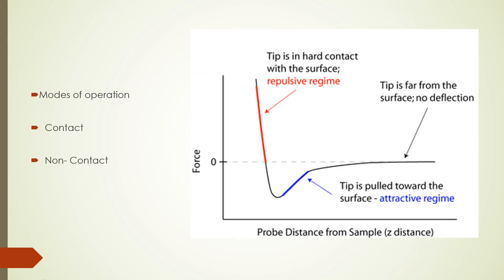The atomic force microscope has two modes of operation: contact mode and non-contact mode. Looking at the force profile, there are two regions — one in which the force is repulsive and one in which it is attractive. In contact mode, the tip is in hard contact with the surface so it experiences the repulsive force, while in non-contact mode the tip stands just above the surface and experiences the attractive force.